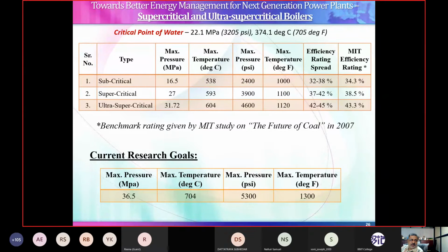Then next we can think of supercritical. 27 megapascal, that is 270 bar. Maximum temperature 593 degrees centigrade. And the efficiency range is 37 to 42%. And MIT is 38.5%. We can still go ahead and go for ultra supercritical, 31.72 megapascal, that is 317.2 bar, 604 degrees centigrade, and the efficiency spread is 42 to 45%. MIT is 43.3%. That means by just switching one boiler to ultra supercritical, you are improving the efficiency by nearly 10 to 12%. The current research goal is 36.5 megapascal, that is 365 bars, 704 degrees centigrade, efficiency greater than 50%. This is the current research goal.